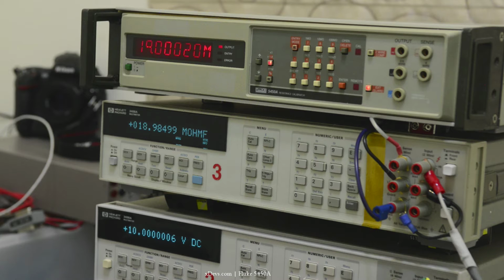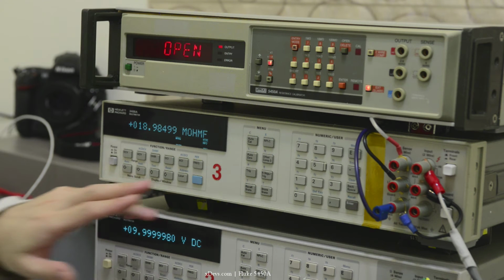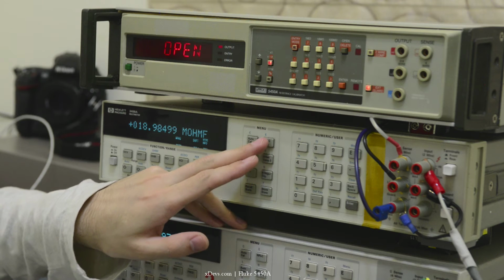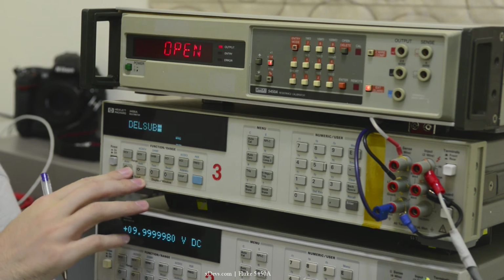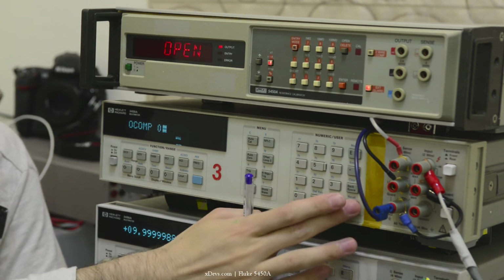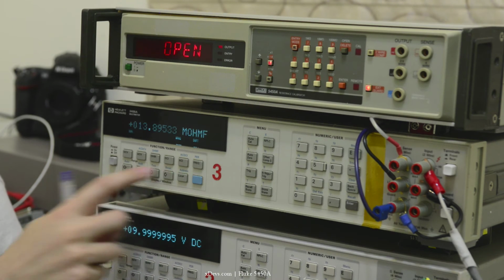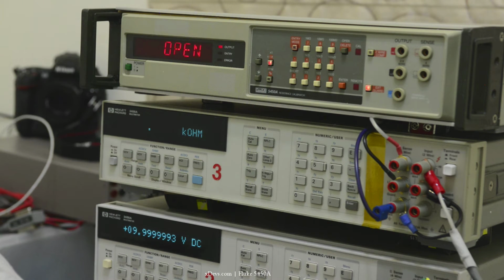Okay, so our value is 18.98499 megaohms. Okay, and I think the next one is open. Yep, nothing there, and open. So essentially, this should show us nothing. Let's set delay 0, offset compensation 0, and auto range, and to work mode. Yep, nothing there. Alright, so that's it for now. Let's open the meter up. Not the meter, the resistance box.